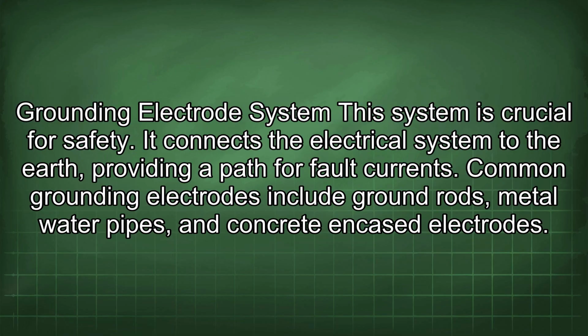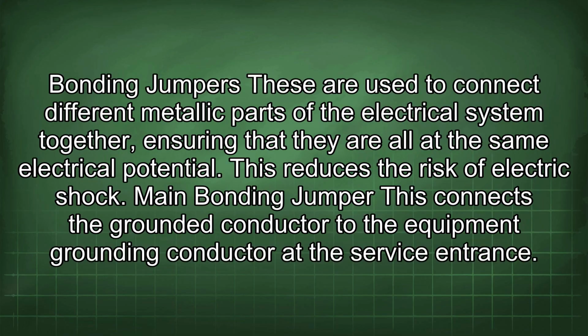Grounding electrode system. This system is crucial for safety. It connects the electrical system to the earth, providing a path for fault currents. Common grounding electrodes include ground rods, metal water pipes, and concrete encased electrodes. Bonding jumpers. These are used to connect different metallic parts of the electrical system together, ensuring that they are all at the same electrical potential. This reduces the risk of electric shock.